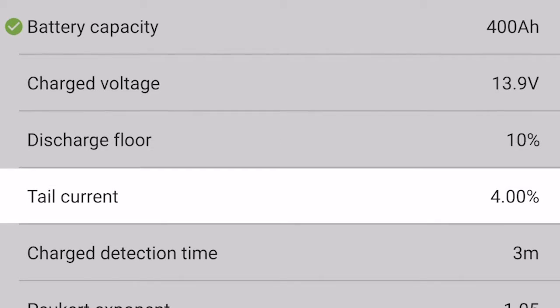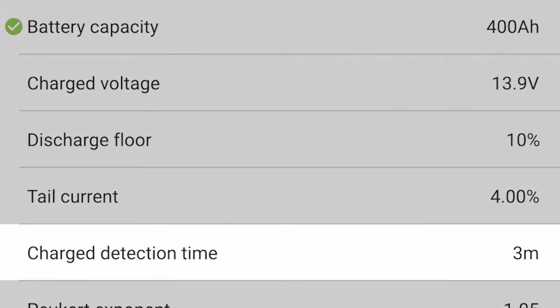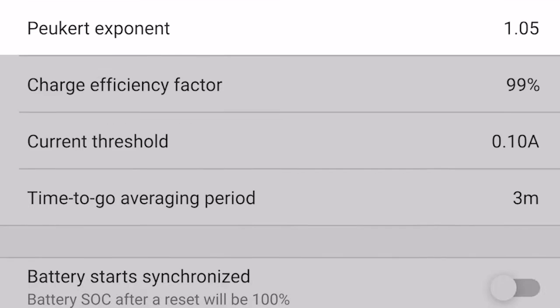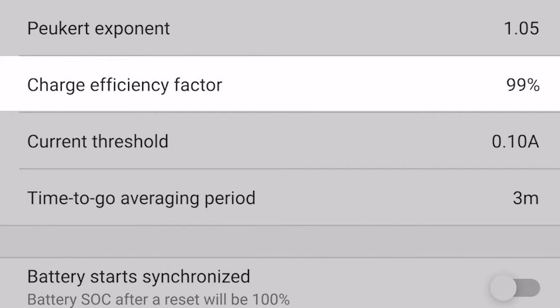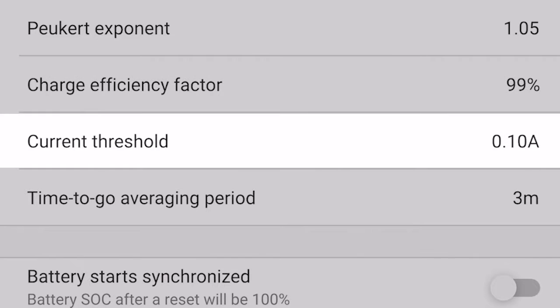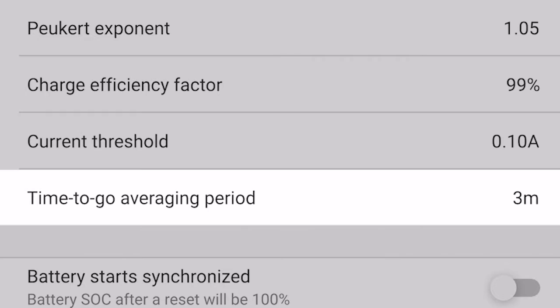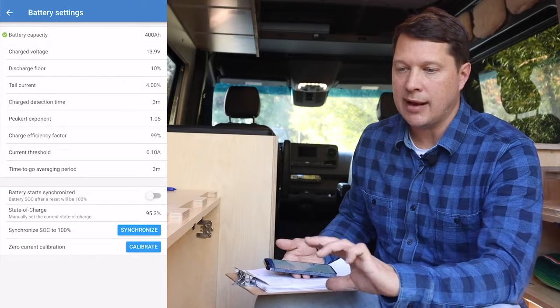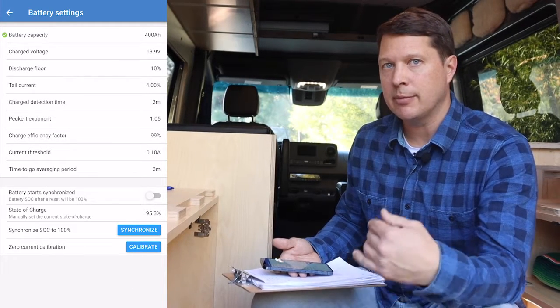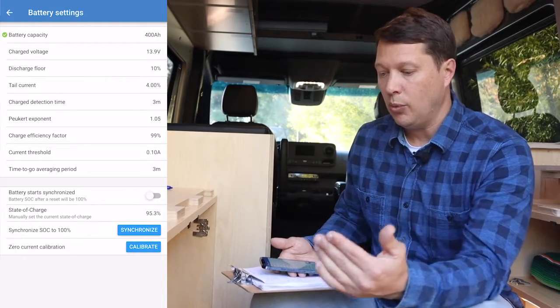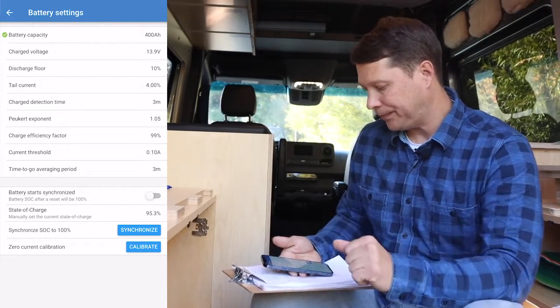Next up is the tail current, and that should be set to 4%. The charge detection time, 3 minutes. The Peukert exponent, 1.05, and this is a change from the factory defaults that are in here. Charge efficiency factor should also be changed. That should go to 99%. You can leave the current threshold at 0.1 amps. And then the time to go averaging period, 3 minutes. That's just how long it is averaging the current amp draw to determine how much time you have left with the power that's in the batteries.